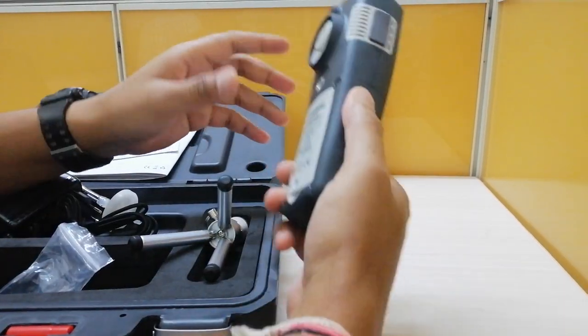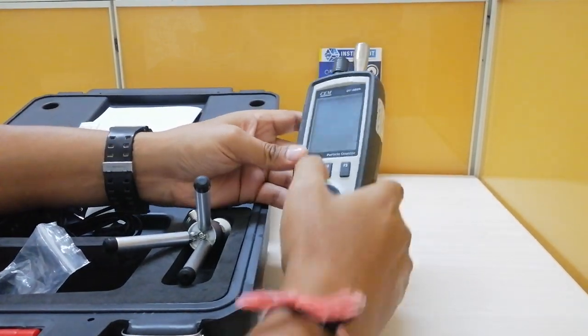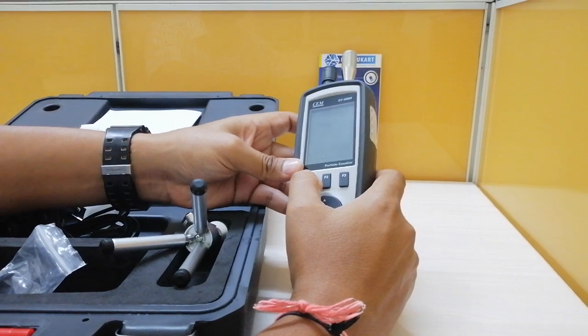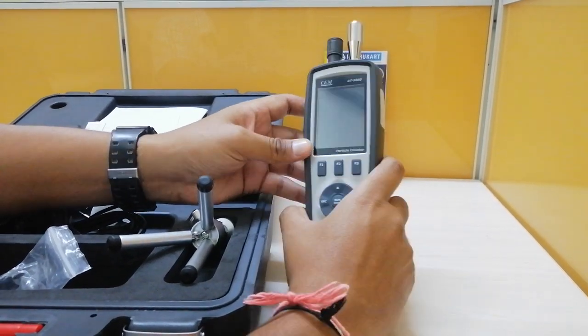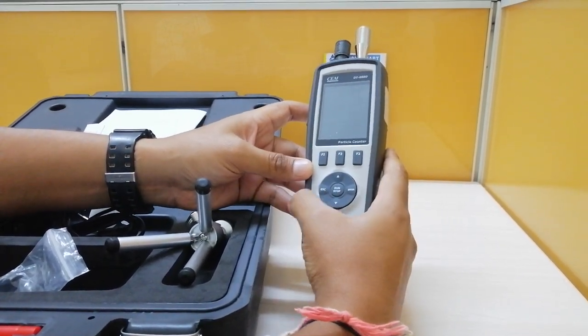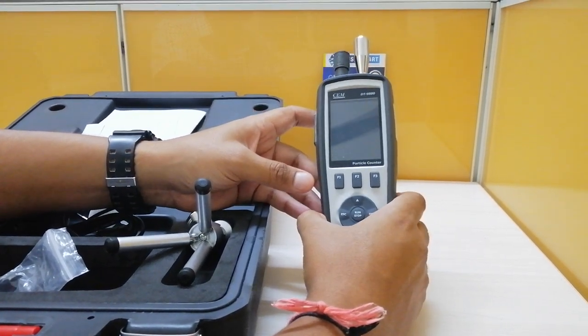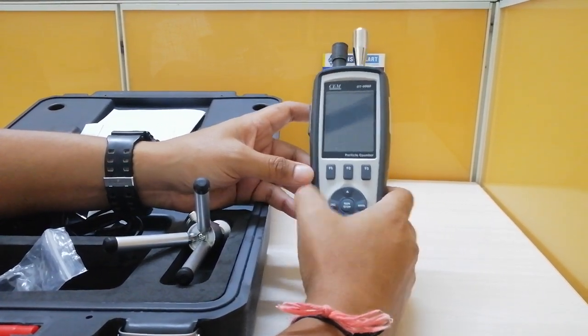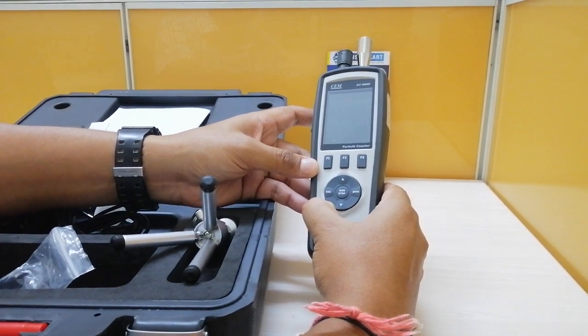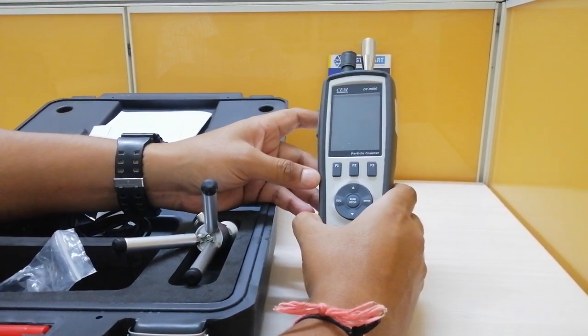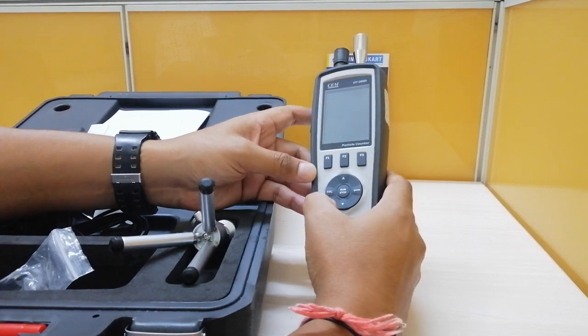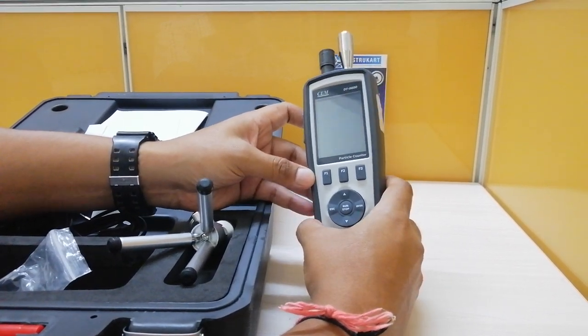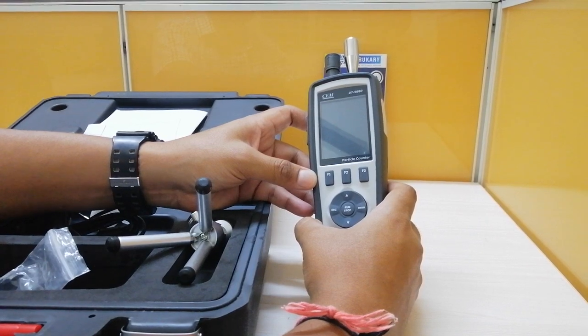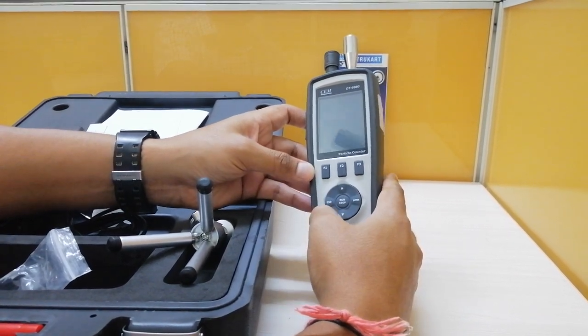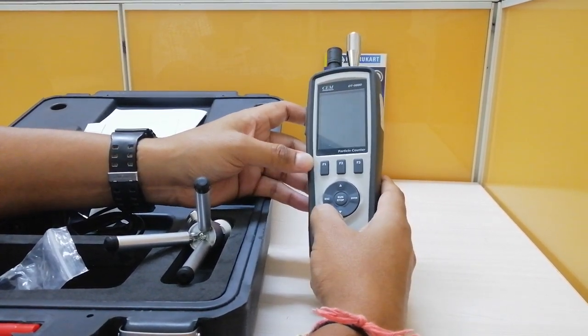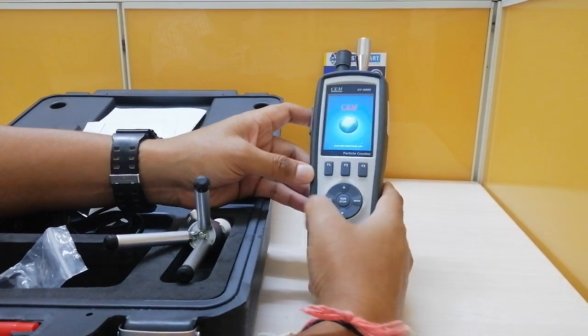Okay, so we'll just try to put this on. Before that, I would like to tell you the specifications for this particle counter. It has channels of 0.3, 0.5, 1, 2.5, 5 and 10 micron, and the flow rate is 0.1 cubic feet, which is 2.83 liters per minute. The count mode is total, differential and concentration, and the coincidence loss is 5%.